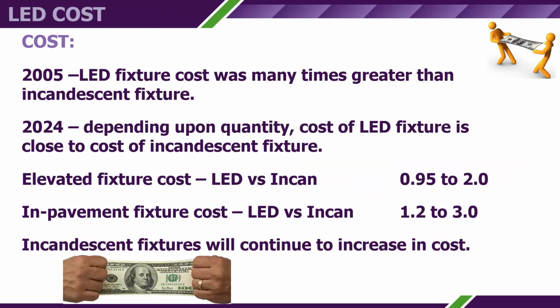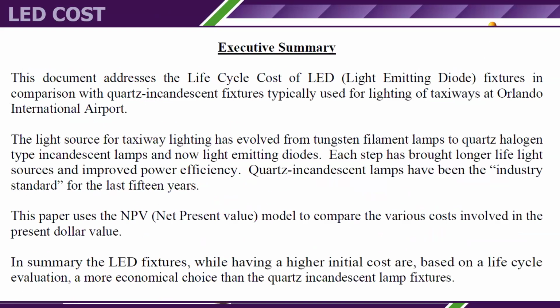Cost. In the early 2000s, cost was very significant. We ended up doing a project for a large airport where we were putting in taxiway center lines and taxiway edge lights, LEDs, in 2004. In order to do that, we had to generate a life cycle cost analysis to justify to the FAA why they should be paying more for these fixtures than what the quartz incandescent would have cost them. And the life cycle cost analysis was able to demonstrate that over a 20-year period, the airport would save roughly about $100,000 over 20 years for using LEDs versus the quartz incandescents.